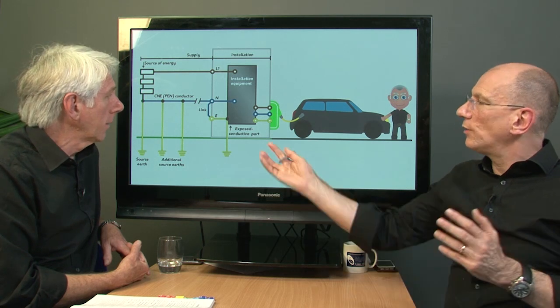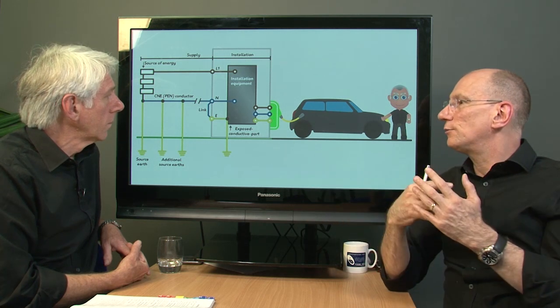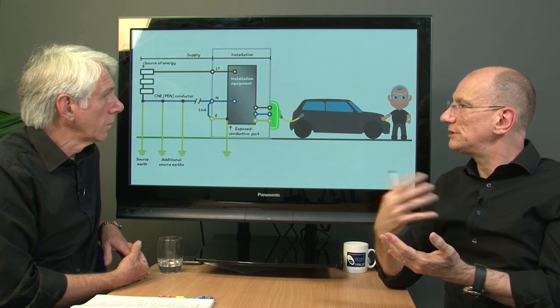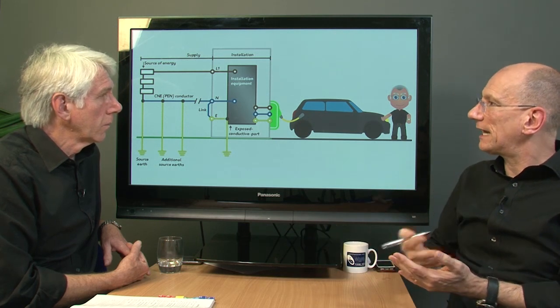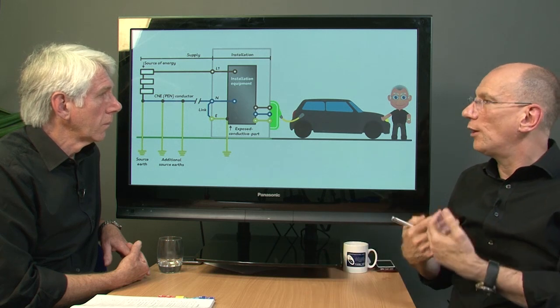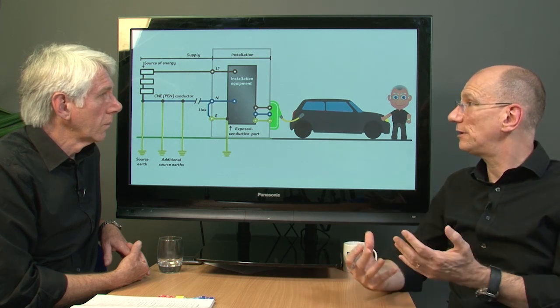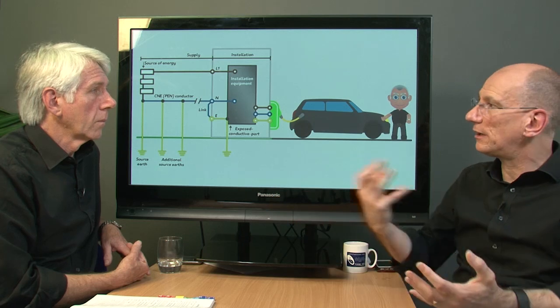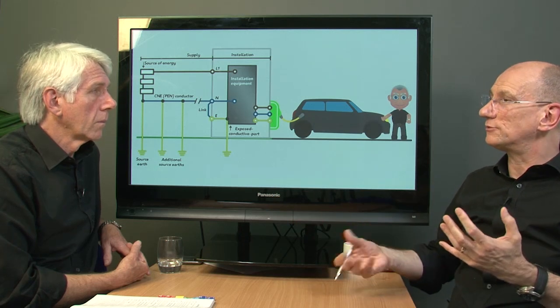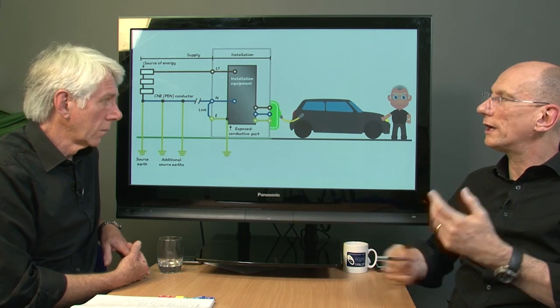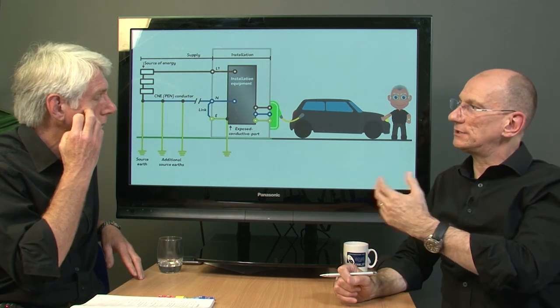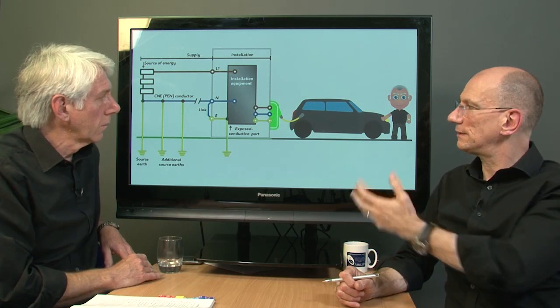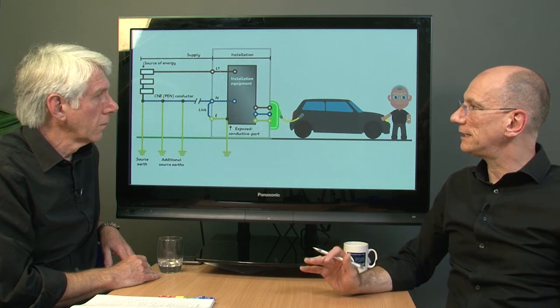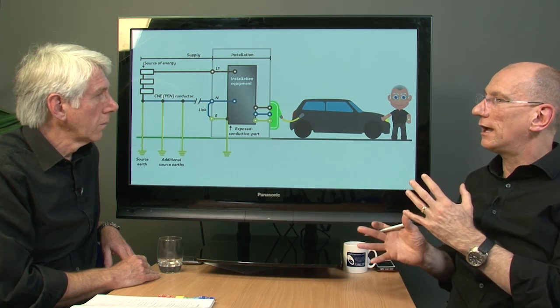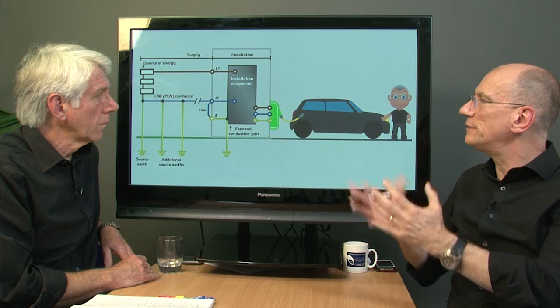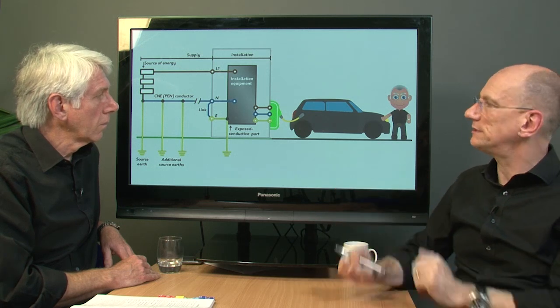What's happened over a number of years is we've gone from gas and metallic pipes supplying our properties, and lead pipes coming into the property, all being replaced with plastic pipes. So we've lost all our parallel earth paths, so it's getting more and more difficult. So this was one solution. Whether we see foundation earthing coming in to supplement this, we'll see, but basically it's an option to help eliminate the risk, or minimise it - I'm not going to say eliminate, minimise is probably a better way.